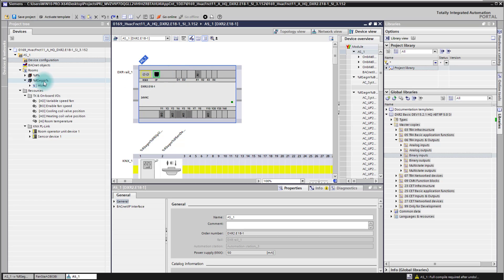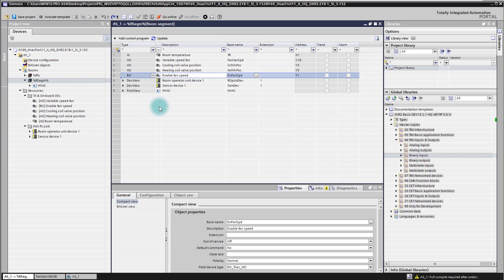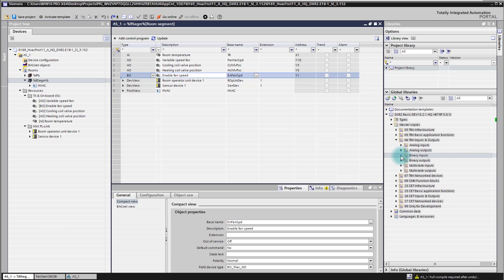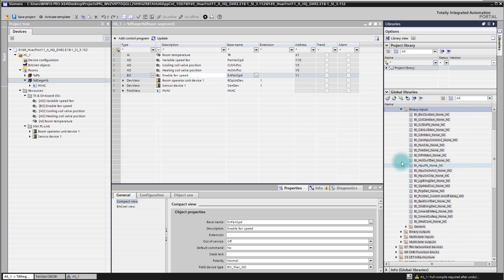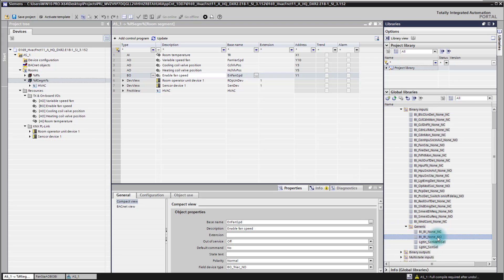When we start now here in the room segment we see first of all we need to have a binary input which can then be connected to a signal where we want to have the possibility to manipulate the fan in addition to the standard application function. I will add here a binary input. I will use a generic one, normally open.